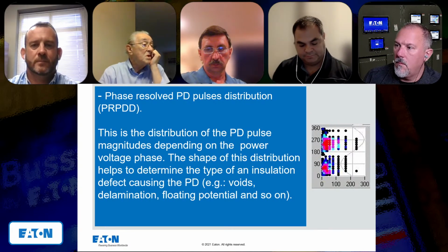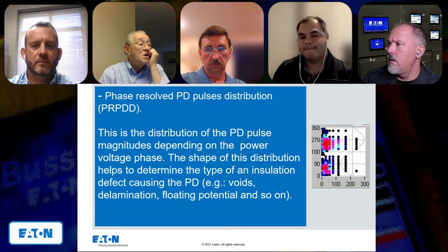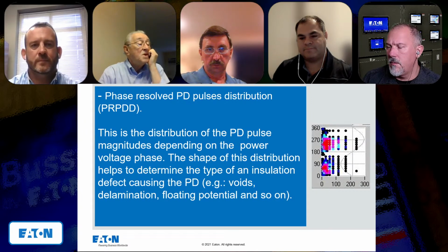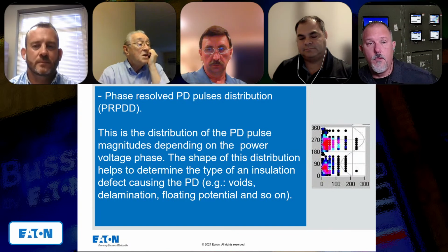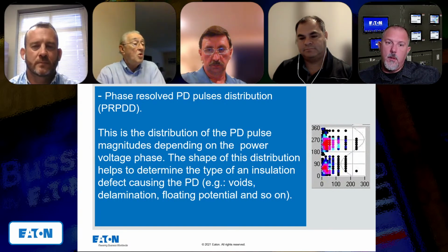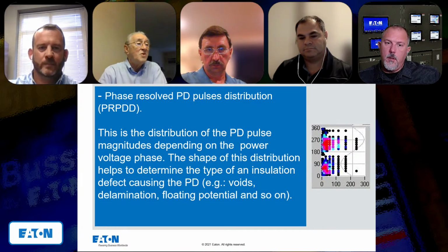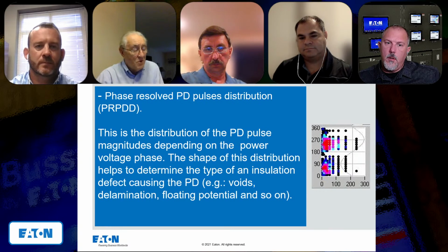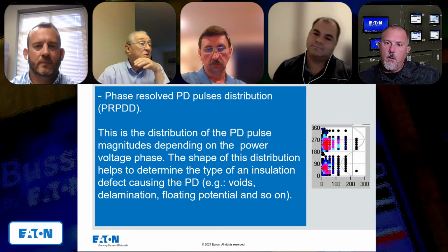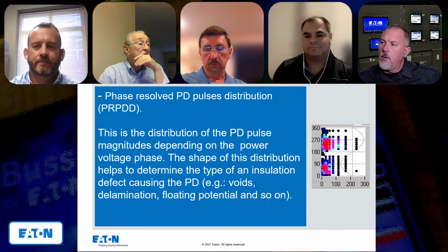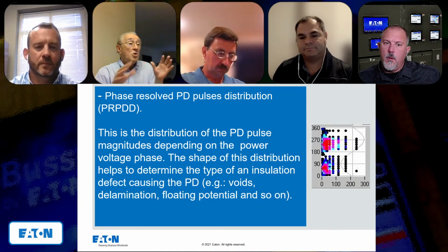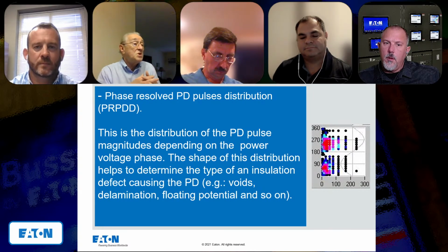And as you can read here, the shape of this partial discharge can help to detect the reason for the partial discharge: voids, delamination, floating potential, and so on. But it is a very complex task to say what type of defect it is, because usually equipment has several defects and they have different shapes. And when you see all of them together, it's very hard to separate.